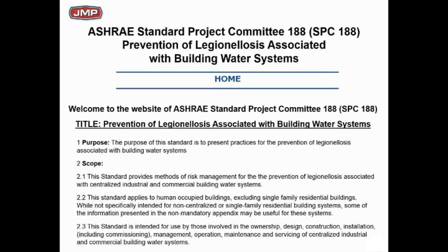There are some issues with Legionella. The number one issue I told you about a little while back, and this might be a little good news for you: they recognize that Energy Code 90.1 telling you to cycle the circulator on and off, and OSHA telling you to run it continuously, is a problem. So they're trying to work through those conflicts, but at the same time take care of the Legionella problem, which in essence is going to mean we're going to have to, somewhere in this flow loop, heat the water to 140 and kill the Legionella. That's what's going to happen. It's going to be a lot more complicated than that, but that's where we're headed.